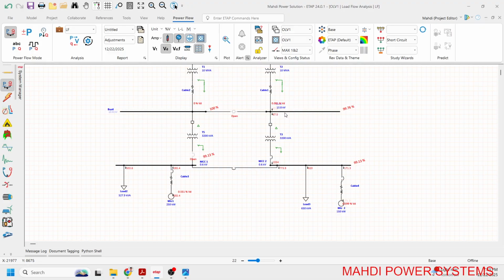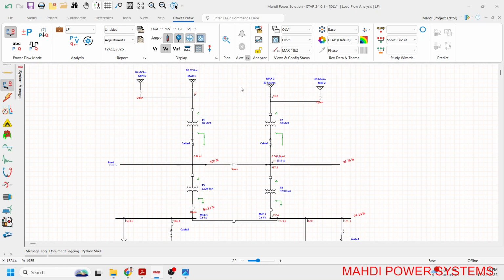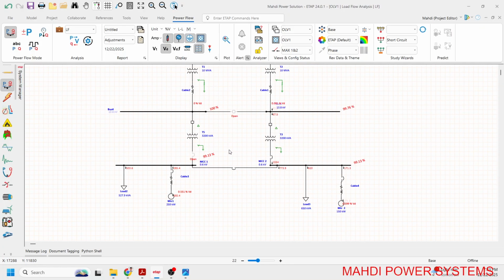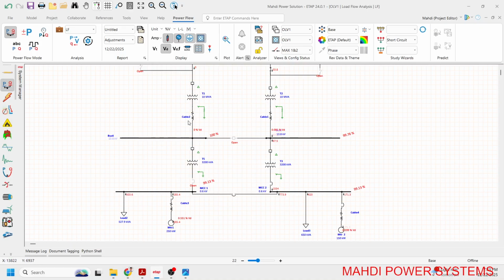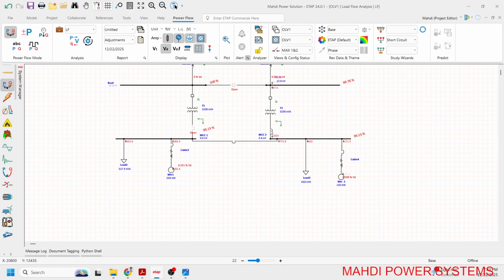We have 13.8 kV at the upstream. There are two networks, one of them a network of maximum short circuit, and each network has a maximum and minimum short circuit, and two transformers here come to two buses, with a 13.8 kV coupler between them, and after that it is transferred to 600 volt with two transformers, and we are at the lowest level of the system.